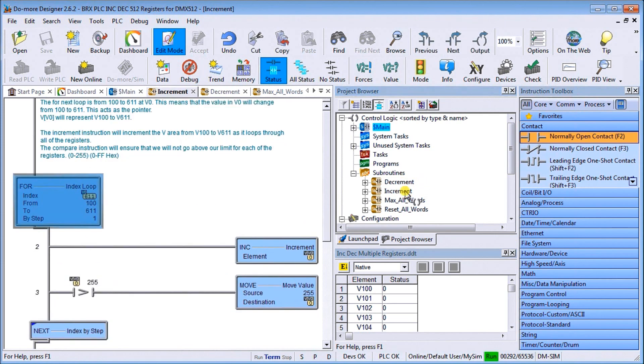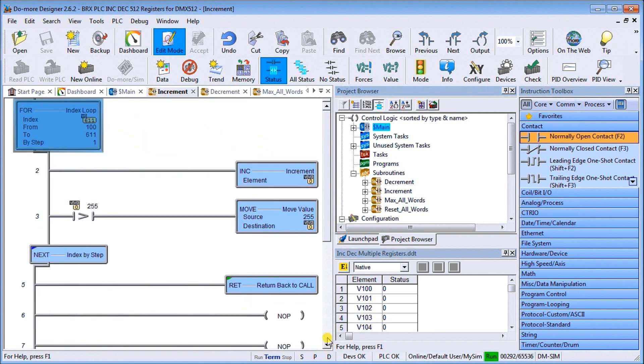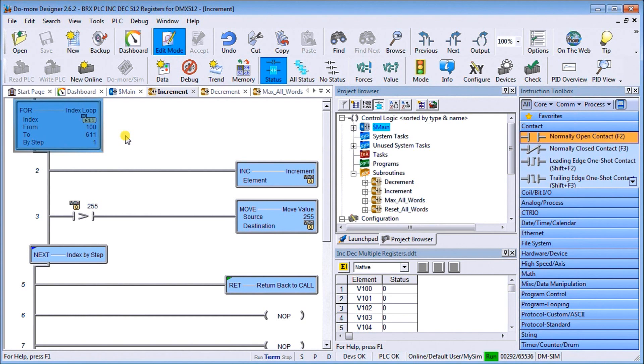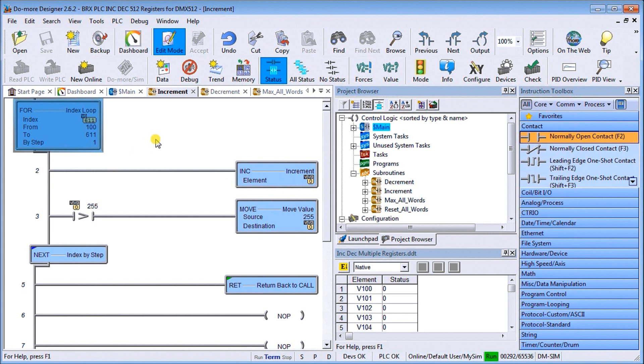Let's go to the increment routine. In increment we'll set up a for-next loop and my index here is V0. We're going from 100 to 611 that specifies my pointer for my indirect addressing. So we're going to be filling up V100 to V611, the 512 registers, and we're going to step by one.